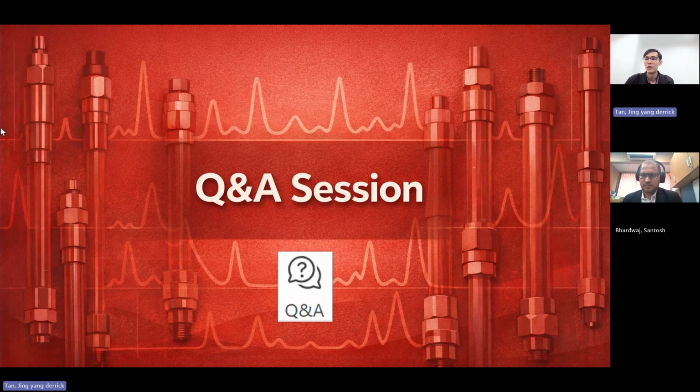Regarding composition, the most problematic thing about IPA is its high viscosity, which creates higher back pressure. But other than that, I believe going up to higher compositions like 100% IPA is still possible. Is there anything Dr. Santosh would like to add? No, Dr. Eric, I think you covered the subject. Yeah, thank you.